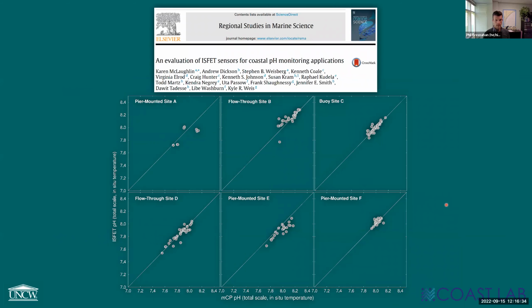A semi-independent study looking at a whole bunch of DuraFets deployed across mostly Southern California found a really similar story. What we're looking at here is 6 different subsets, or subplots, of meta-cresol purple, which is considered the gold standard for measuring pH in the laboratory, versus the ISFET or DuraFet pH on the y-axis here. And you can see there's scatter about that 1-to-1 line, and a perfect sensor to discrete sample matchup would of course have all of the points falling right on that line, which is not at all what we see here.